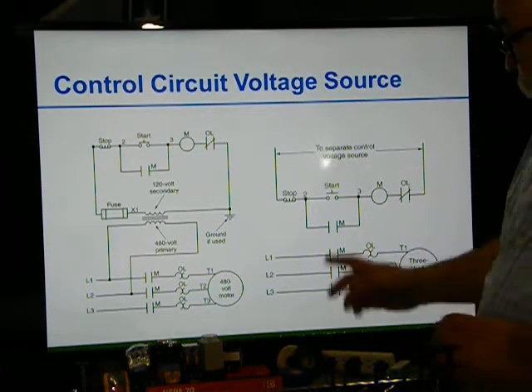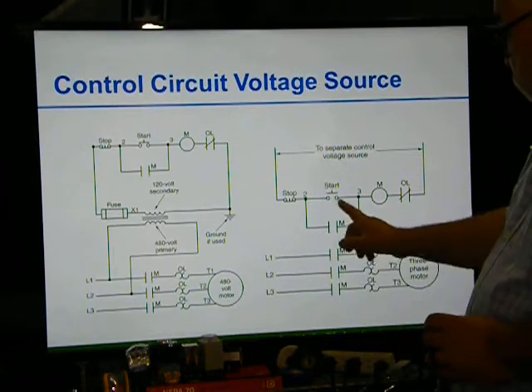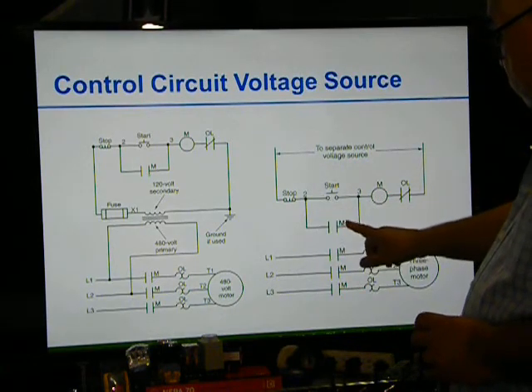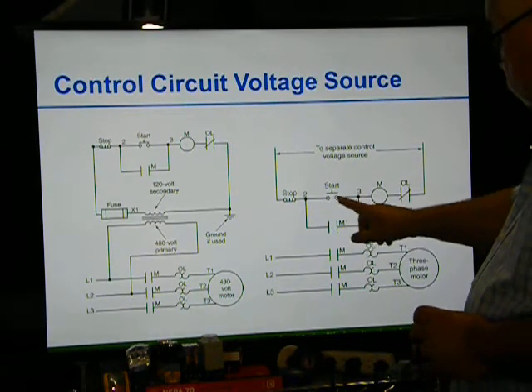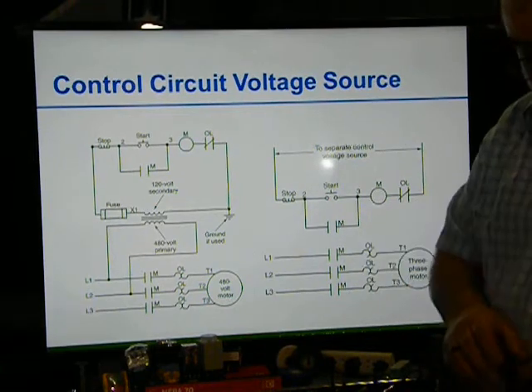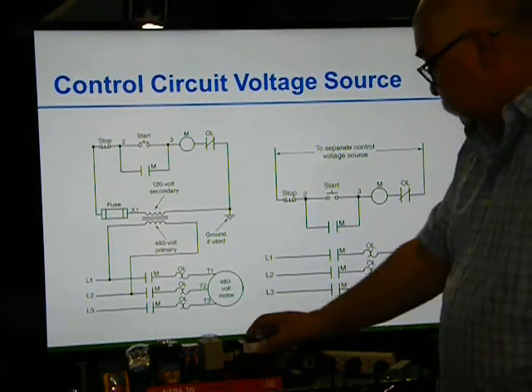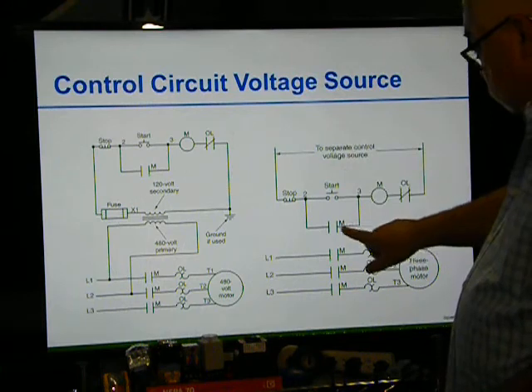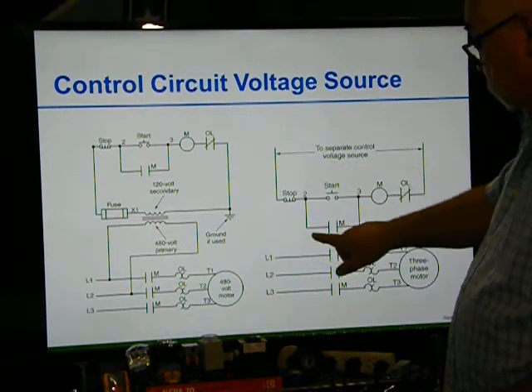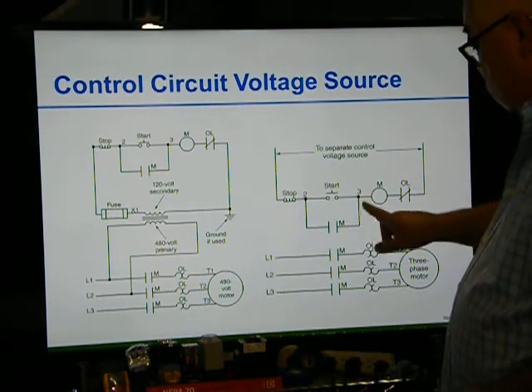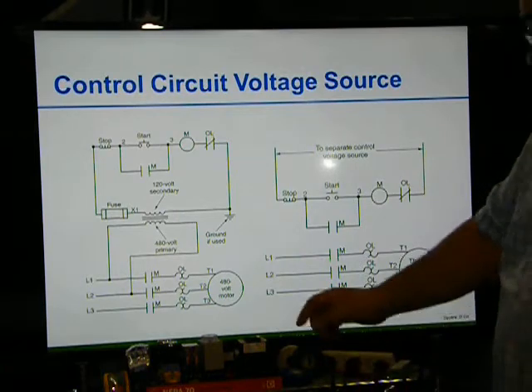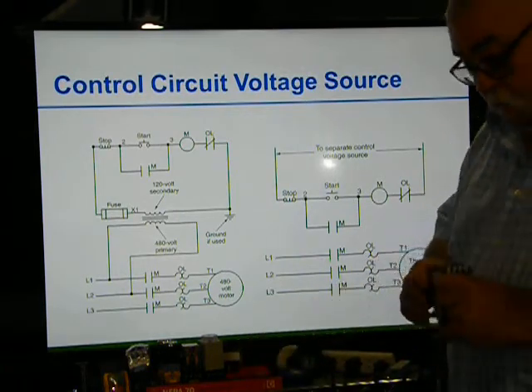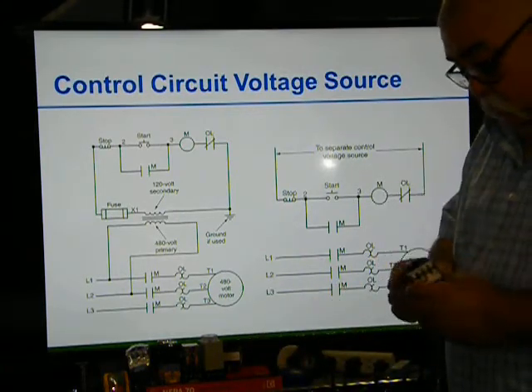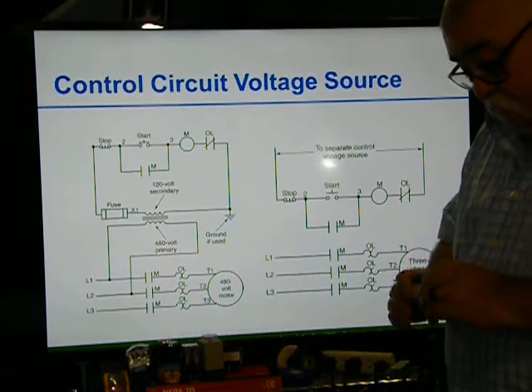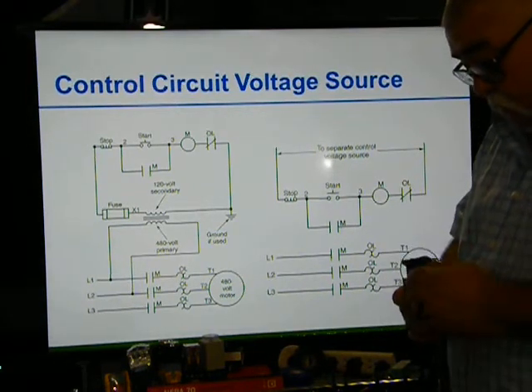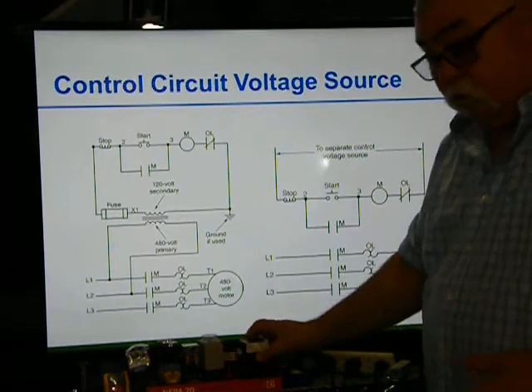Okay, so once the power comes across, and since that power is going across here, because this will bring it down this way. Once you hit the start, the voltage comes this way and this closes. So I always use this as my 3 and then this as a 4. The reason I do it that way is because of these contactors that I use. They're inexpensive, and they're easy to use. So that's why I buy these.